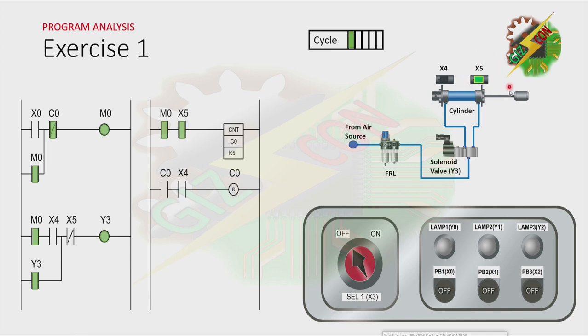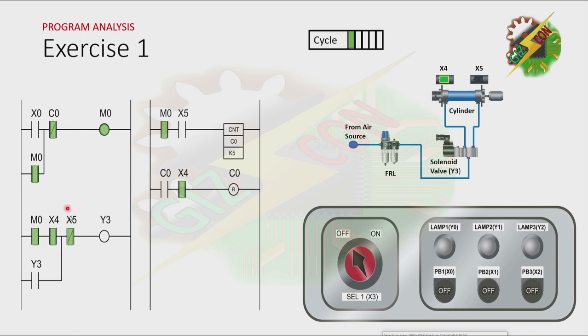Now the cylinder reaches the fully extended position. That will cause X5 to turn on. And because X5 turns on, it will cause the count value of counter 0 to increase. The normally closed contact of X5 will open, which will cause Y3 to turn off and the cylinder to retract. Then because the cylinder retracts, it will cause X4 to turn on again. And because M0 is on, it will cause Y3 to turn on again, and the cycle will repeat.